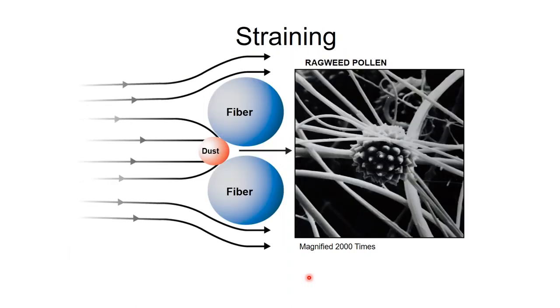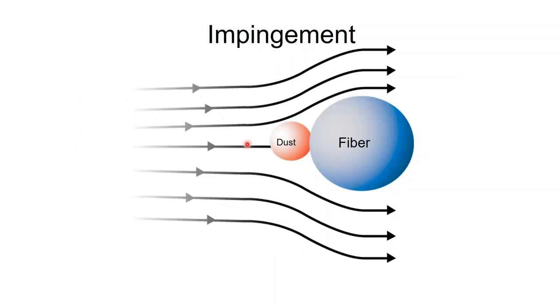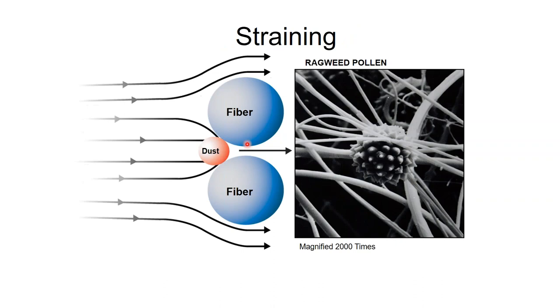Third is straining — like a pasta strainer, particles too big to fit through the holes get blocked. Once particles clog those holes, subsequent particles impinge on what's already there, and the filter does an increasingly good job. The dirtier the filter, the better it filters — but it also creates more pressure drop. At some point the pressure drop becomes too much for the equipment and we're starving airflow, so it needs to be changed.